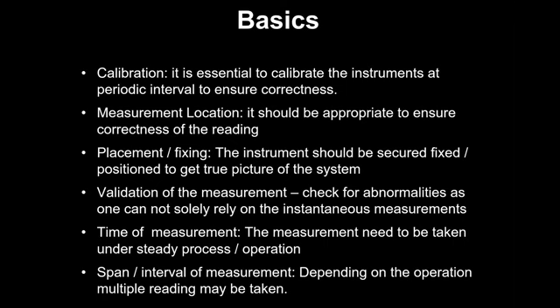Because it was a big plant, they had a power plant also. They had their own online display also, so that on the DCS the oxygen content and CO level were displayed. When we did the measurement, our oxygen was coming considerably higher, indicating that excess air was much more, is what our instrument was showing, whereas in their DCS the values were correct. They were showing around 3.5% oxygen and 300 ppm of carbon monoxide, whereas what we were showing was almost 8 to 8.5% oxygen and correspondingly less carbon monoxide.